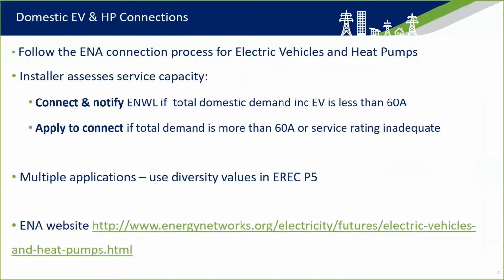Under the process, the installer may assess the suitability of the electrical service to accommodate the EV or heat pump. Using rules set out in the IET wiring regulations, the installer determines the total domestic maximum demand, including the device. If this is less than 60 amps, and the installer judges the service is rated at 60 amps or more, they may connect and notify Electricity North West, subject to other checks. If the load calculation determines a maximum demand greater than 60 amps, they must apply to connect using the standard application process.